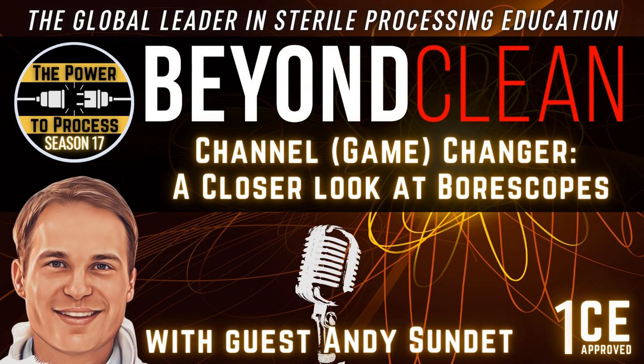Yeah. So here's how we've tried to simplify it. This is not any kind of brain surgery that we've come up with, but I don't know what you're going to find. The permutations are endless, but it's going to fall in one of four categories. It's going to be either debris, something in there that does not belong. With a borescope, you might have been able to feel that with a brush in the past, but now you're going to know if it's a round lumen or if there's something hanging there that shouldn't be. So debris is the first thing. Damage, a lumen that doesn't look like the rest of the lumen. It's either kinked or there's a big scratch in it. Those are some of the real common ones that we see. So damage is the second one.